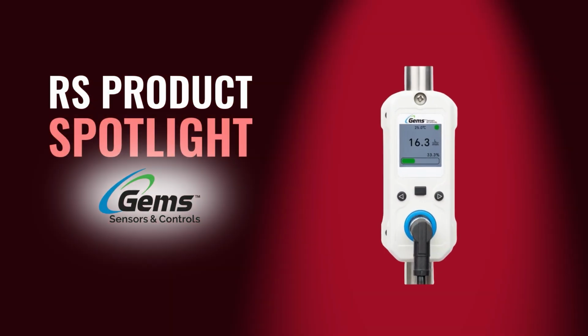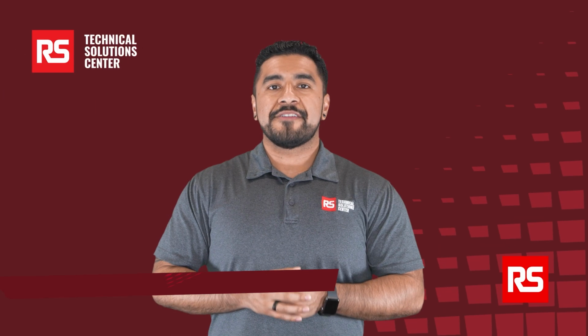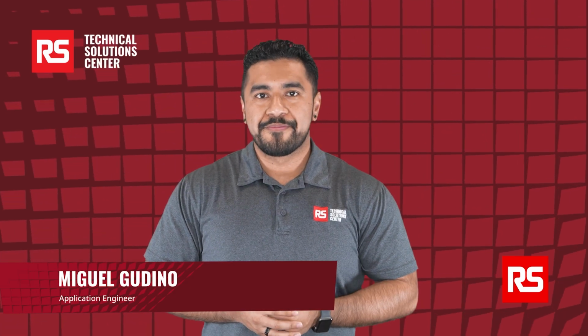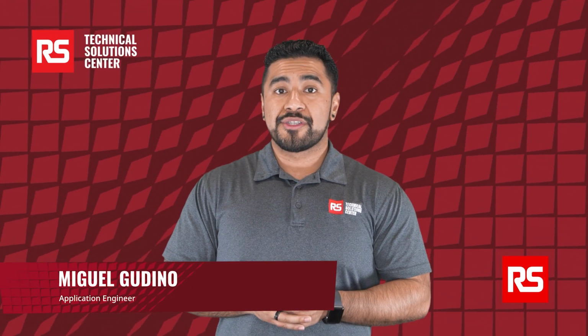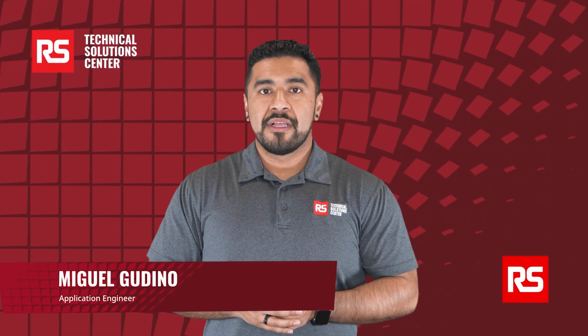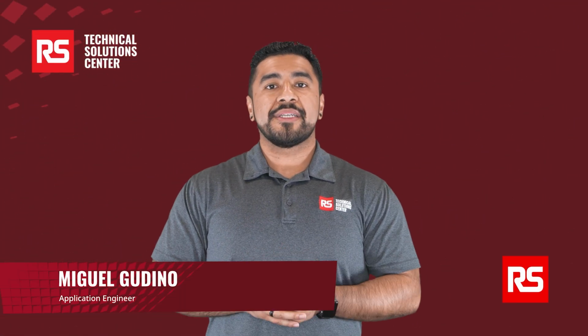Adding flow measurement to an existing system doesn't mean hiring a pipe fitter or plumber, adding potential leak points in the system, or taking equipment offline. In today's RS Product Spotlight, we're introducing the GEMS XFT Clamp-On Ultrasonic Flow Meter, a compact, non-invasive flow solution designed for fast installation, long-term reliability, and seamless integration.